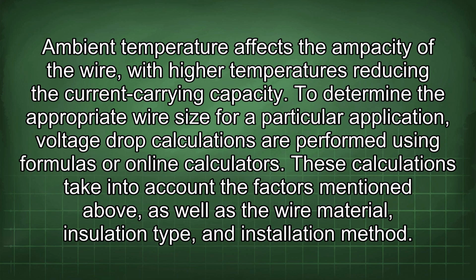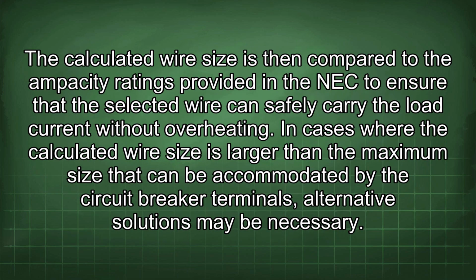To determine the appropriate wire size for a particular application, voltage drop calculations are performed using formulas or online calculators. These calculations take into account the factors mentioned above, as well as the wire material, insulation type, and installation method. The calculated wire size is then compared to the ampacity ratings provided in the NEC to ensure that the selected wire can safely carry the load current without overheating.